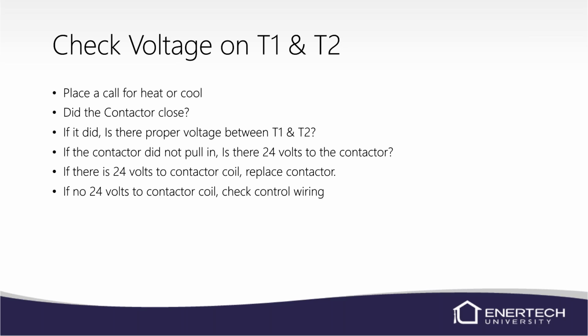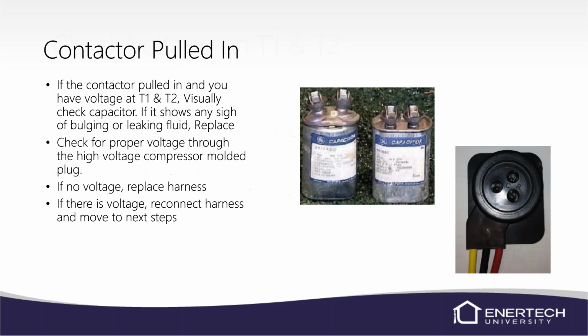But just make sure you have 24 volts, obviously, to the contactor. So it runs basically from the thermostat to the lockout board. Make sure all the safeties are closed, and then it goes to the contactor. If the contactor pulled in and you have voltage at T1 and T2, make sure you check the capacitors.